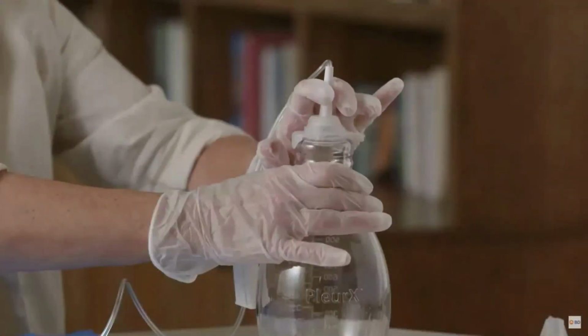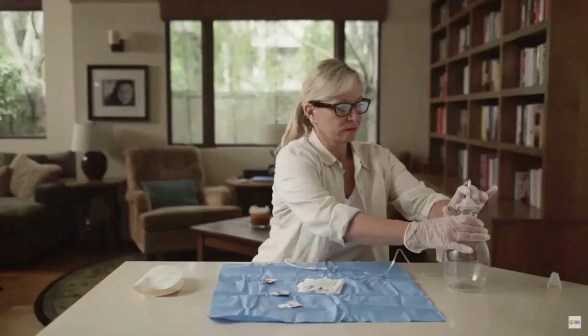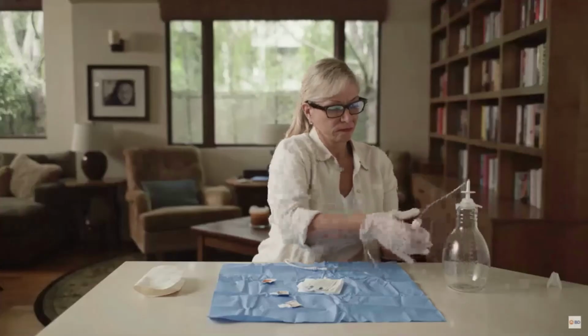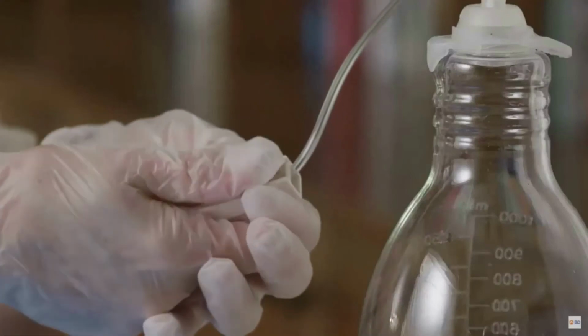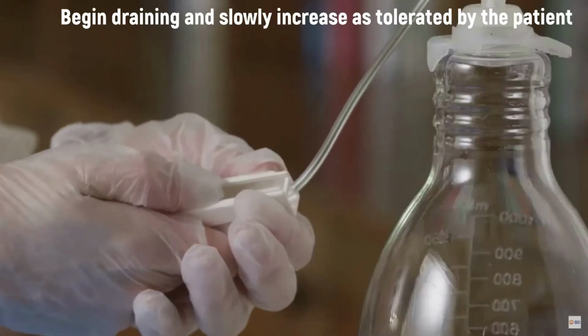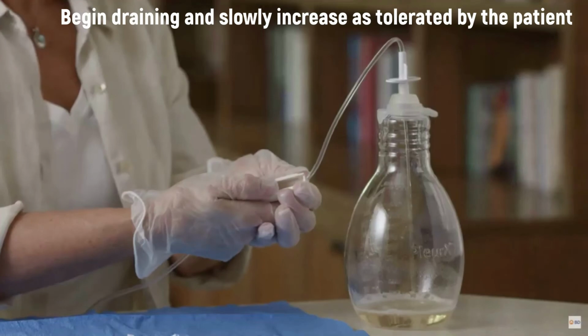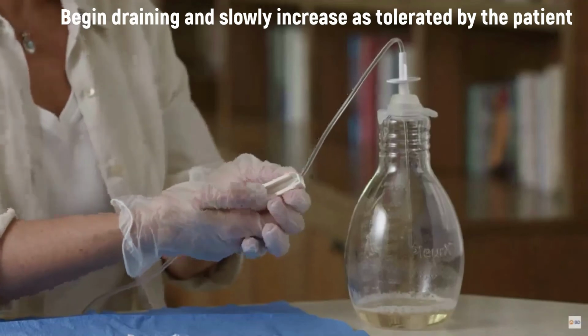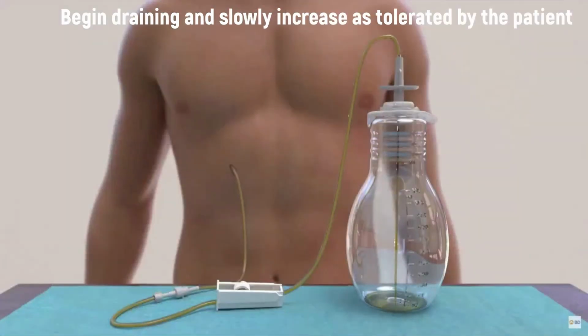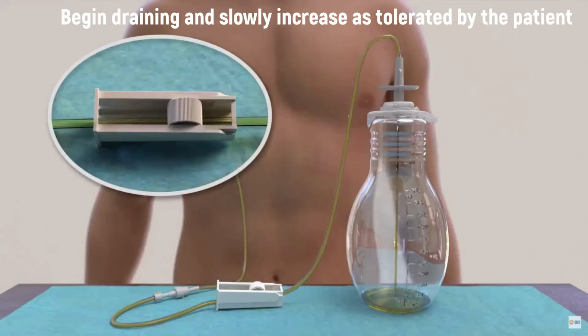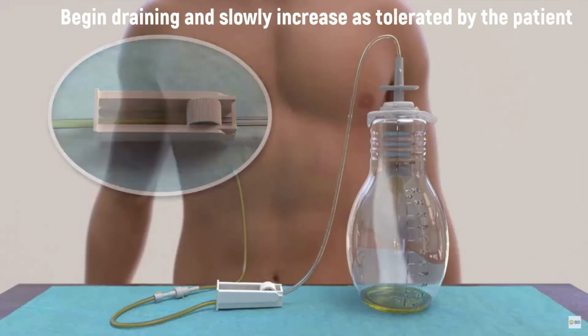Remember that the white roller clamp on the drainage line is still closed. To begin draining, slowly open the roller clamp by rolling the wheel away from the bottle. Fluid will start to flow into the vacuum bottle. You can adjust the flow by moving the wheel on the roller clamp as desired to open or close the clamp. Drainage usually only takes 5 to 15 minutes.